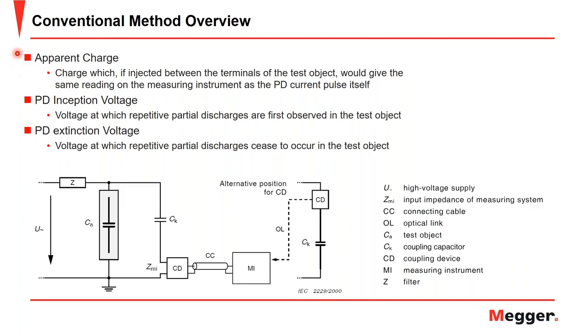So apparent charge, which you've heard a couple times now, is the charge which, if injected between the terminals of the test object, would give the same reading on the measurement instrument as the PD current pulse itself. Since you can't actually measure the PD current pulse, this gives you the apparent charge equivalent to that current pulse. Here we have the PD inception voltage, which is the voltage at which repetitive partial discharges are first observed in a test object, and consequently the PD extinction voltage, which is the voltage at which repetitive partial discharges cease to occur in a test object.